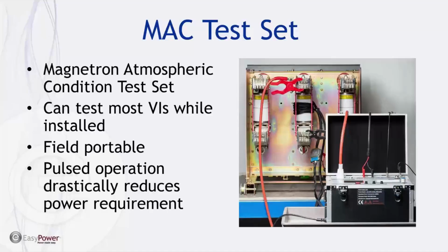And the way that we were able to reduce the weight so drastically is we turned the measurement from a constant measurement like a manufacturer would use to a pulsed measurement. So instead of having to constantly supply current to a magnetic field coil, we are charging a bank of capacitors and rapidly discharging that bank of capacitors to the magnetic field coil, which provides a very strong magnetic field for a very short period of time, but long enough for us to do this measurement.